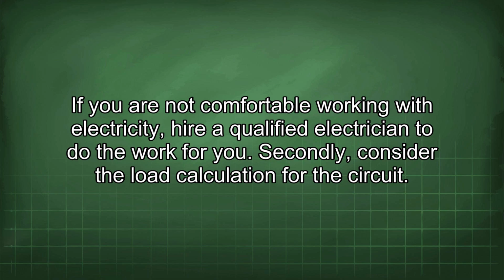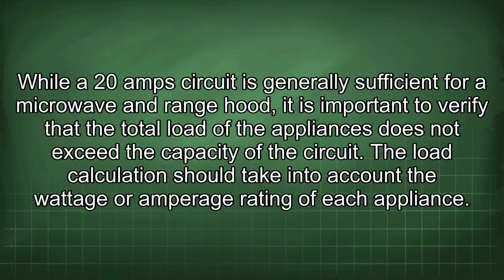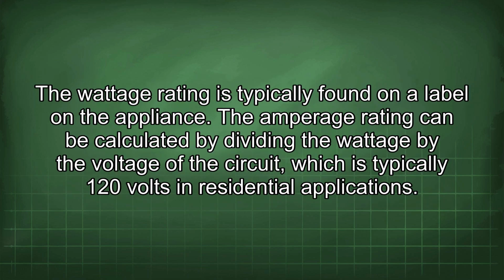Secondly, consider the load calculation for the circuit. While a 20-amp circuit is generally sufficient for a microwave and range hood, it is important to verify that the total load of the appliances does not exceed the capacity of the circuit. The load calculation should take into account the wattage or amperage rating of each appliance. The wattage rating is typically found on a label on the appliance.